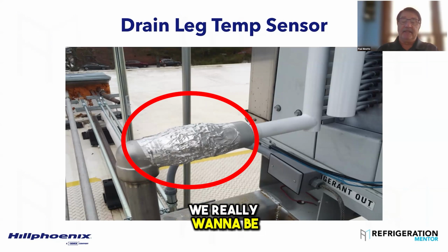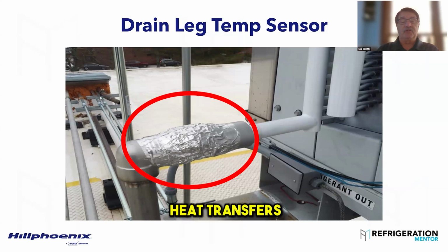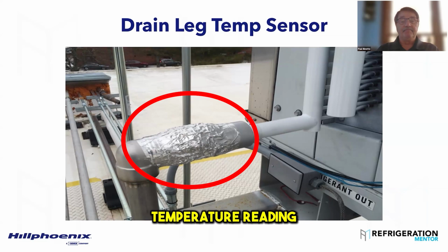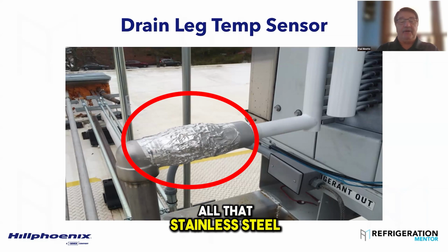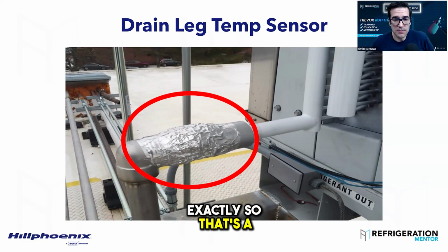In this case, I would have chosen the white pipe because it's thinner and heat transfer is quicker. The way this was mounted is going to cause a lag in our temperature reading because now we're heating up all that stainless steel pipe. Yeah, exactly. So that's a good point. So location is very, very key.